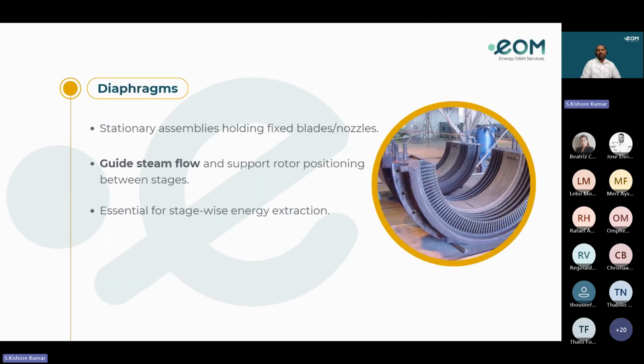Diaphragms. Diaphragms are the stationary assemblies holding fixed blades and nozzles, and they also guide steam flow and support rotor positioning between the stages. They are essential for stage-wise energy extraction. Because of their robust design, they are cast or forged and come in split assemblies, which ensures durability under high pressure, high temperature conditions and facilitates assembly and maintenance.